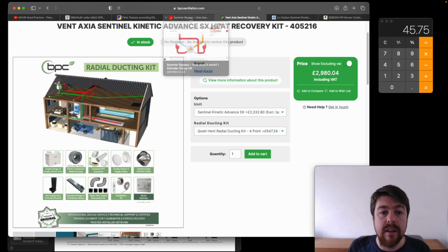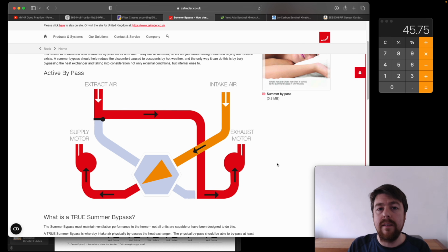The first one is something that occurs during summer. Remember, these units are optimized for cold environments where you want to recover every bit of heat from the exhaust to pass to the air coming into the space. If you're going for a very thermally efficient building, what you don't want is a superheated house with a heat recovery system doing its utmost to overheat it further. So there's a feature with a little valve, a damper actuator, that opens and closes so that the extract air, when it comes from the house heated, doesn't go through the heat exchanger to heat the intake air - it bypasses and dumps straight outside. That was definitely one feature I wanted, and I wanted it transparent - I didn't want to have to go up and rebalance valves myself.